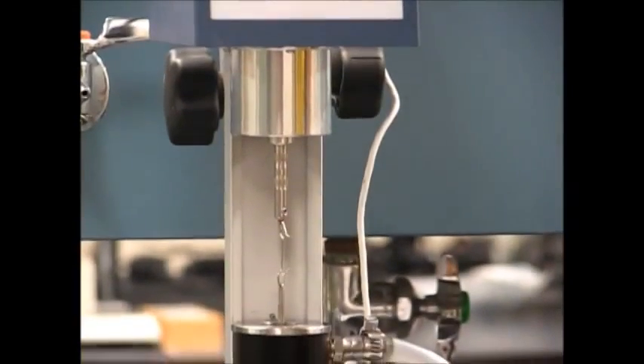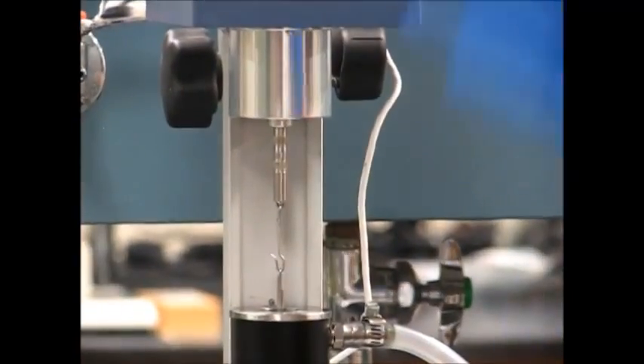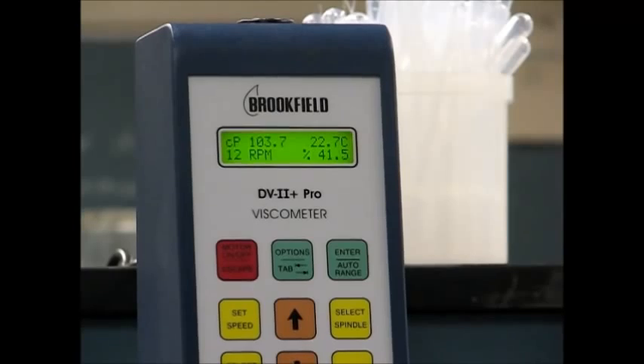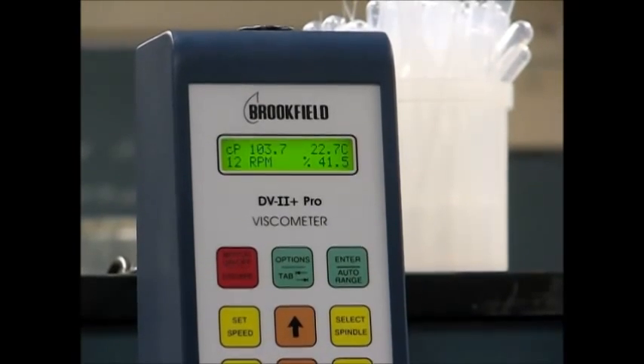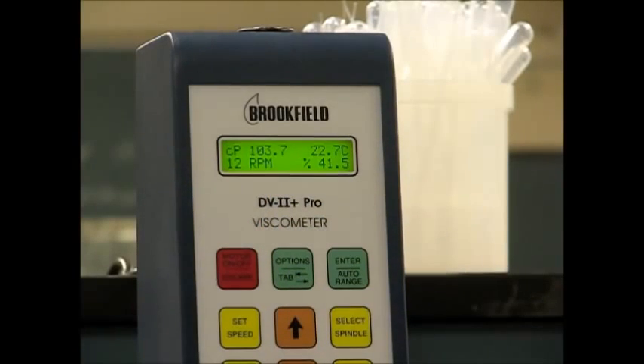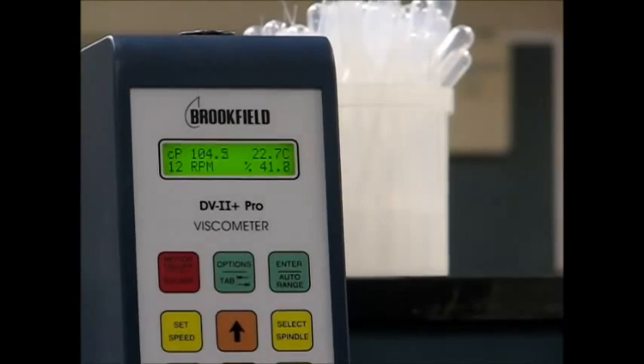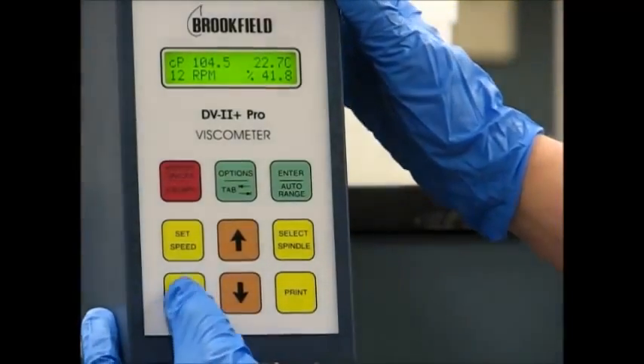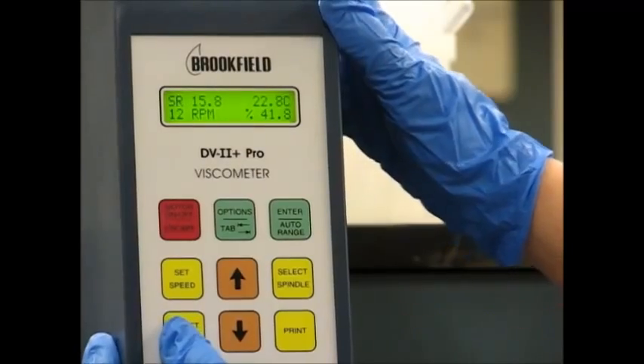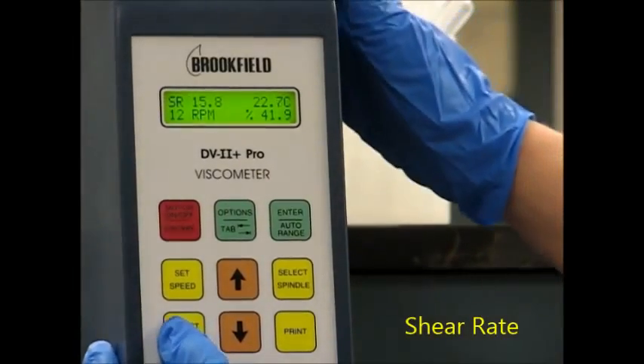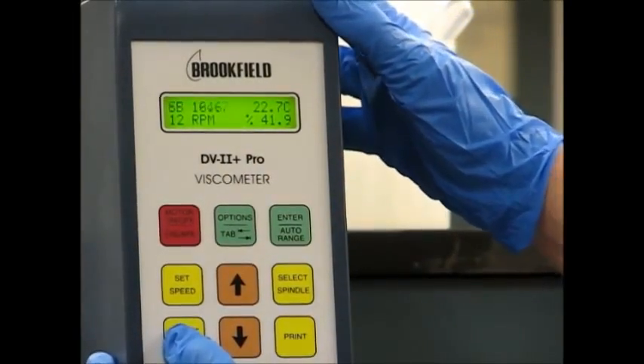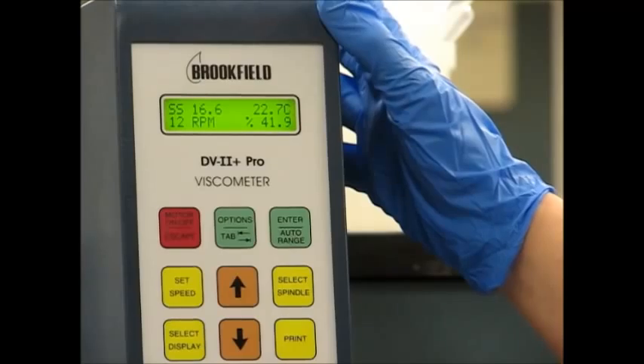Our percent torque says that it's at 41%, which is between our range of 10% and 100%. And it's also telling us that at this rpm, the viscosity of our fluid is around 104 centipoise. We can also use the select display key to display the shear stress. And if you press it again, it also displays the shear rate. So at 12 rpms, our shear rate is 15.8, and our shear stress is 16.6.